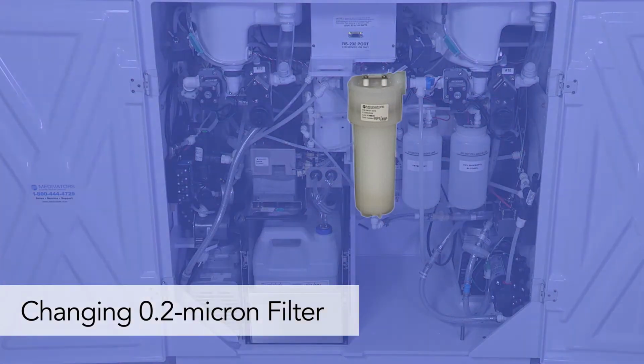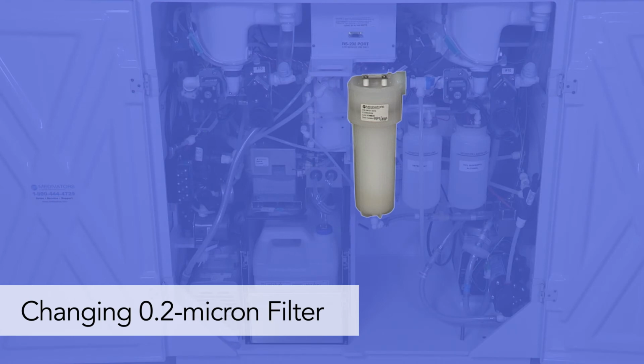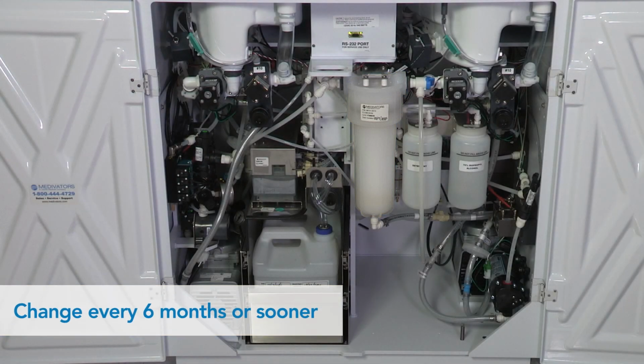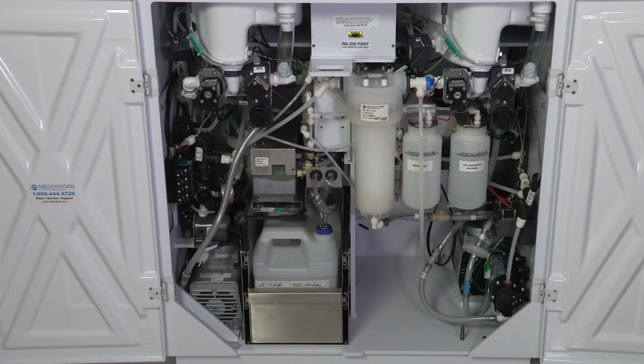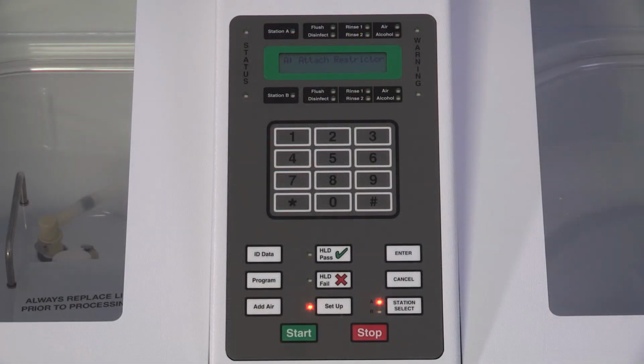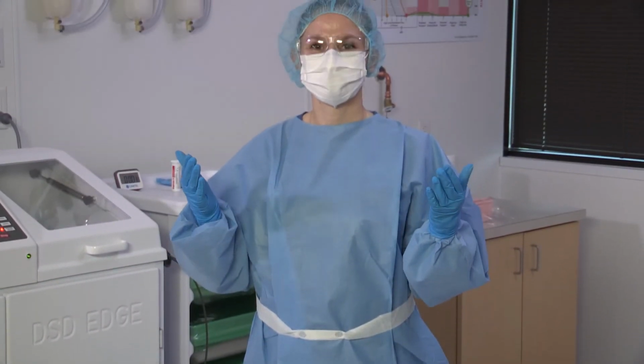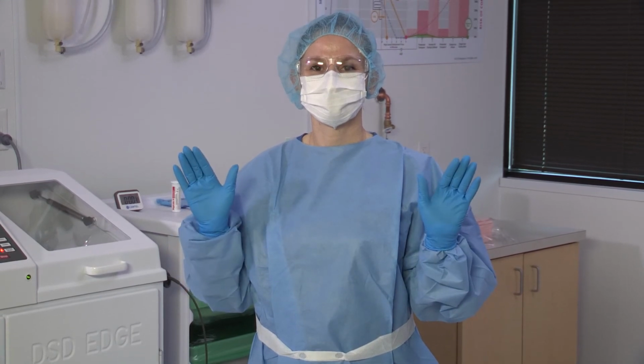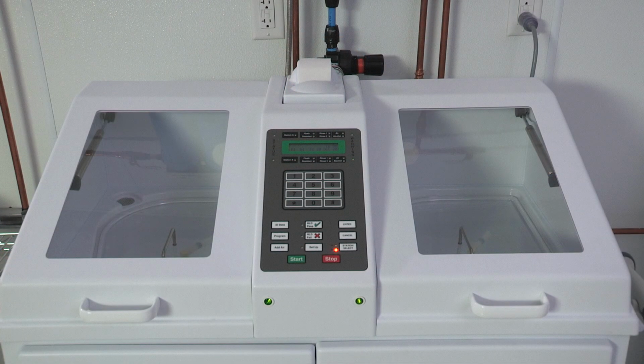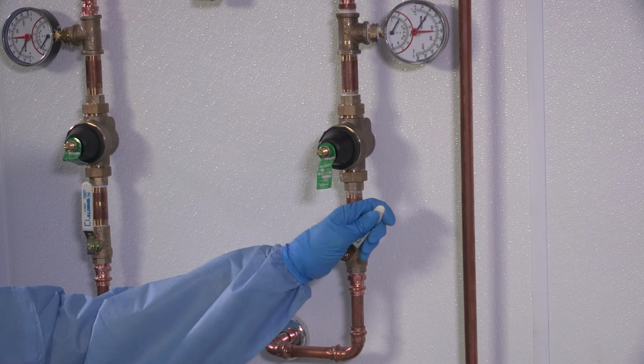The internal 0.2 micron bacteria retentive water filter must be changed every 6 months or sooner, depending on the quality of the incoming water. After this filter is changed, it is necessary to run a waterline disinfection prior to beginning endoscope reprocessing. To change the 0.2 micron filter, don the facility-required PPE. Ensure the unit is idle and the main incoming water supply valve is closed.